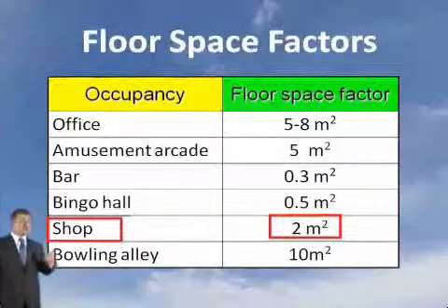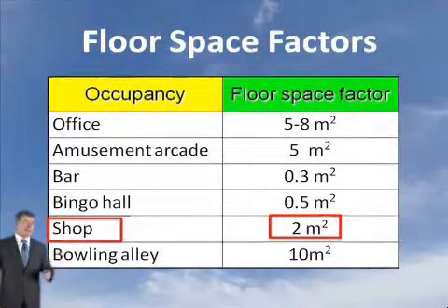For example here, shop, 2 square metres. If you apply that to Tesco's, how many toilets would you have? I'm not even funny. If you went to Tesco's now and everyone's there not moving around because the trolleys are all jammed, would you go in? It's not a reasonable factor. A supermarket might use 6 or 8 square metres. Sometimes the client will tell you, Marks and Spencer's will tell you, we're using a floor space factor of 8 or 10. In other words, the client may tell you that, but you can't just make the floor space factors up. So these are good floor space factors. ADB is different, but any floor space factor you have to demonstrate to the building control or the approved inspector that these are valid floor space factors.